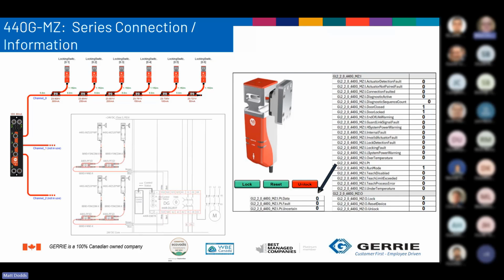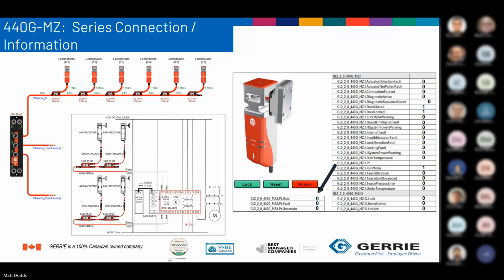If you don't have a PLC, there's also the 440R-2DG that can be used to convey status information and diagnostic information through Ethernet connectivity, so standard Ethernet with the gateway. And the lock and unlock signal is sent through the Ethernet port. So again, that's pretty much the only way to use them with locking and unlocking door switches.